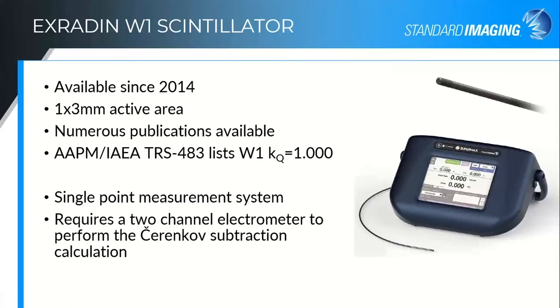Limitations of the W1 are that it is a single point measurement system, designed initially for output factor measurements. It also requires a two-channel electrometer to perform the Cherenkov subtraction calculation. We have the routine built into our Supermax — it will walk you through the characterization and dose calibration, then apply that correction and do the calculation for your later measurements. If you use someone else's two-channel electrometer, you'll have to do the math yourself, but it is of course possible.